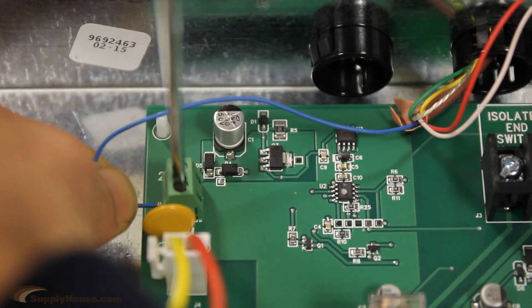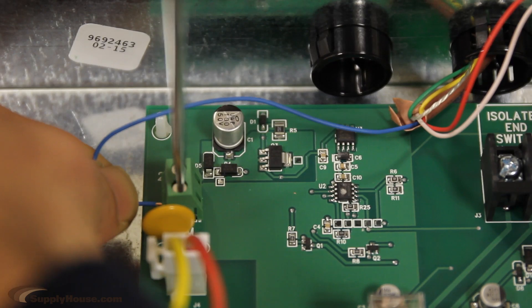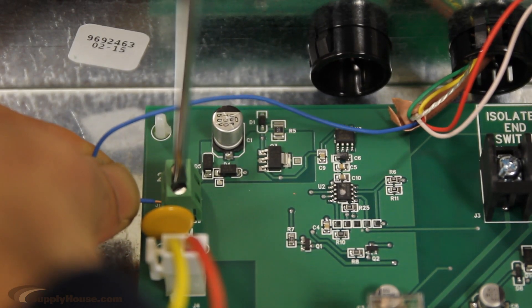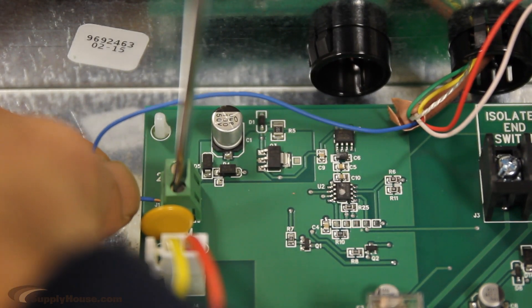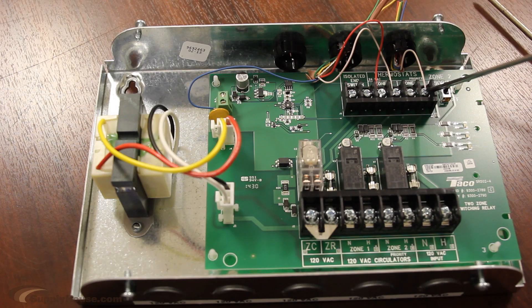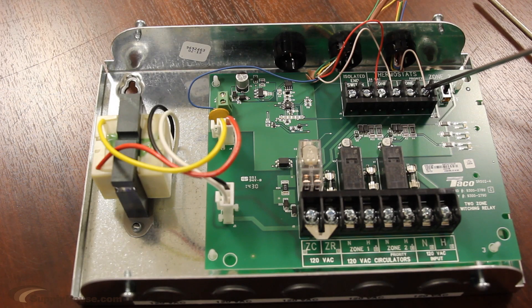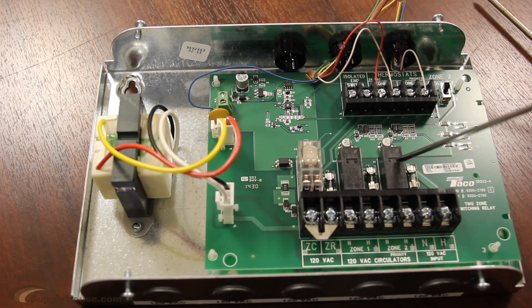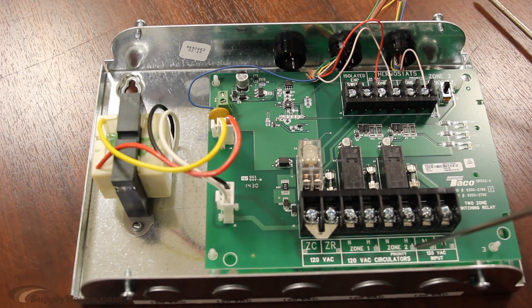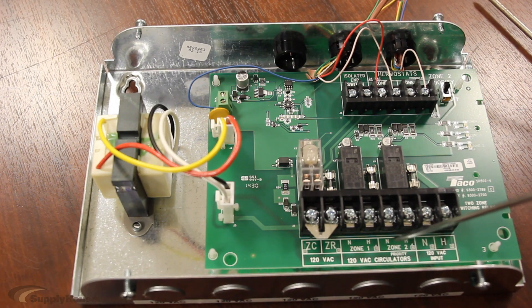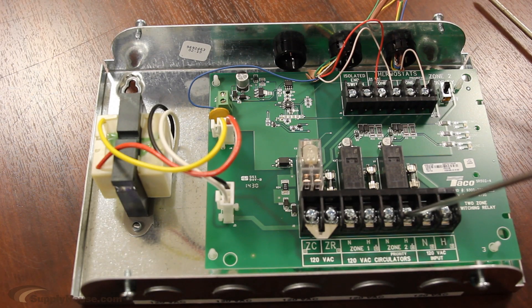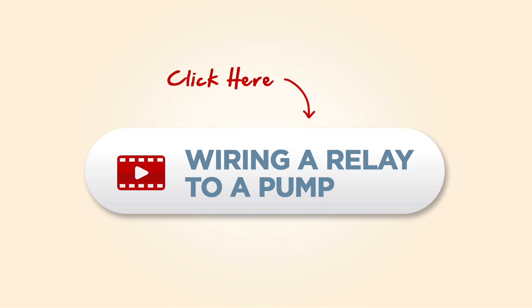The R and the common provide power to this thermostat from the switching relay. Also, do not over-tighten as that can cause the wire to break. Now, the relay will convert the 24-volt signal from the thermostat into a high-voltage signal to activate a circulator pump, zone valve, or actuator connected to the bottom portion of the relay. If you want to learn how to wire a circulator pump to a relay, click here.